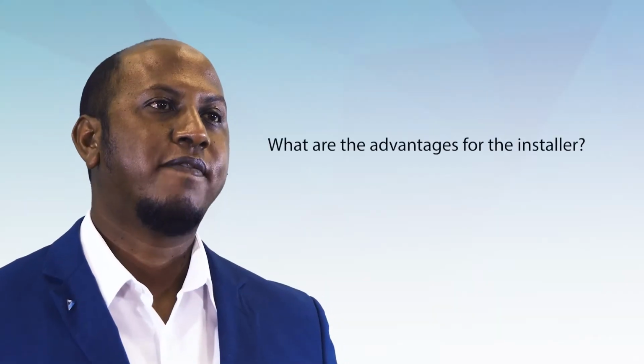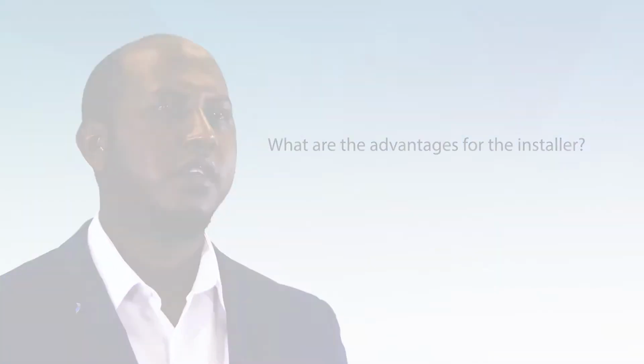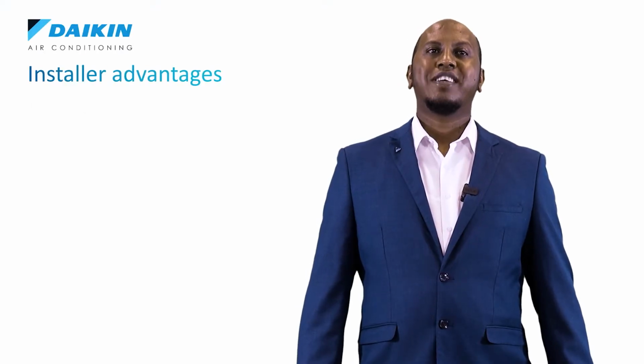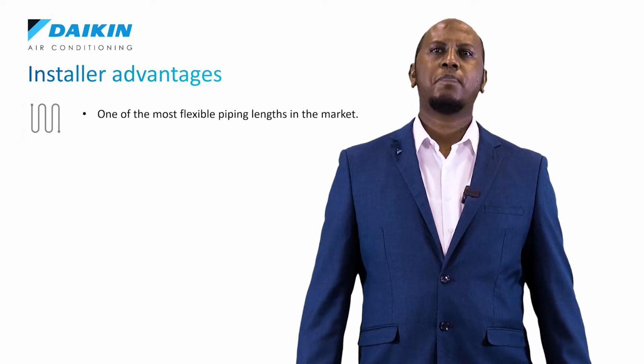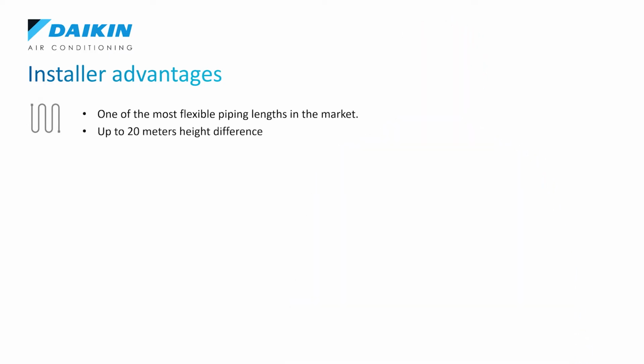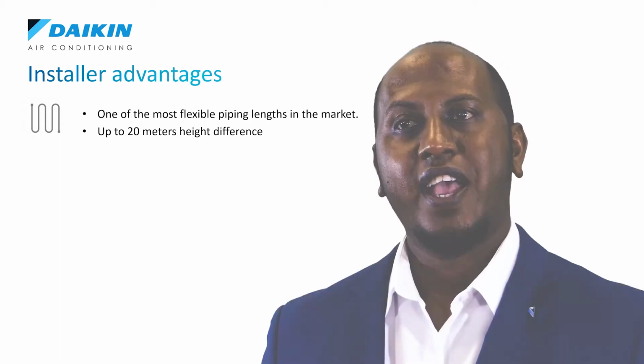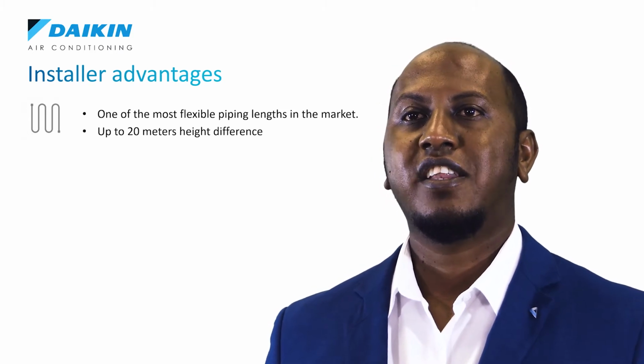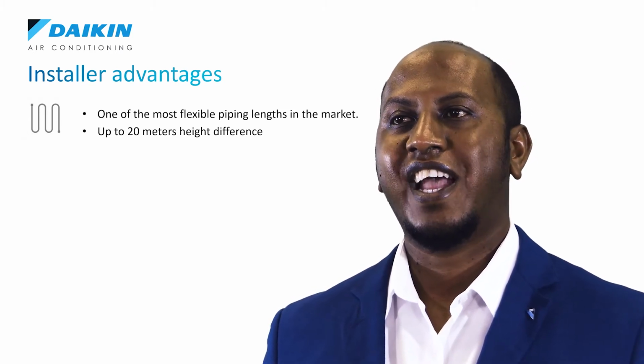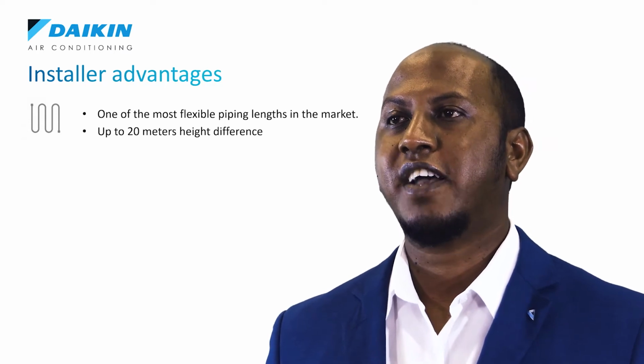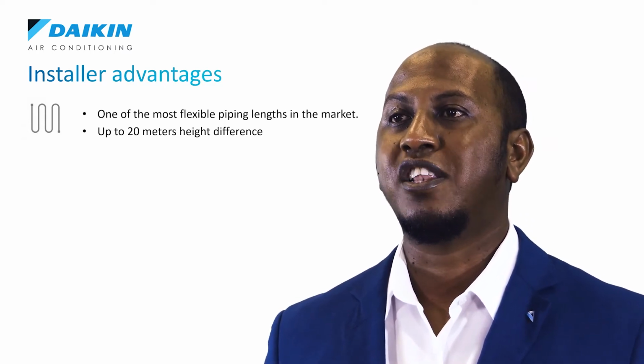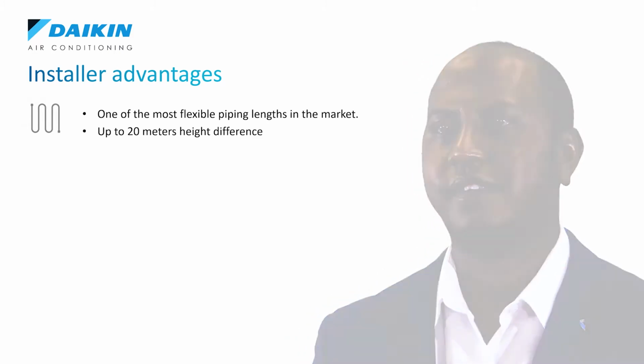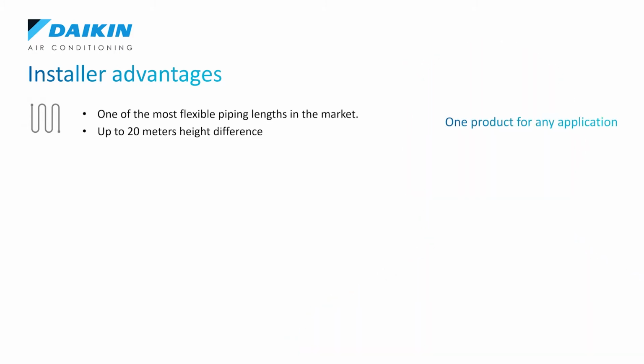Let's have a look at the advantages for you as an installer. From an installation point of view, the Sensira offers one of the most flexible piping lengths in the market. The unit gives you a maximum pipe run of 20 meters on the 2.5 and 3.5 kilowatt units, whereas on the previous range, it only offered 15 meters, and now up to 30 meters on the 5 and 6 kilowatt units with a new level difference of 20 meters. This allows you to tackle any application in the market with a single product.